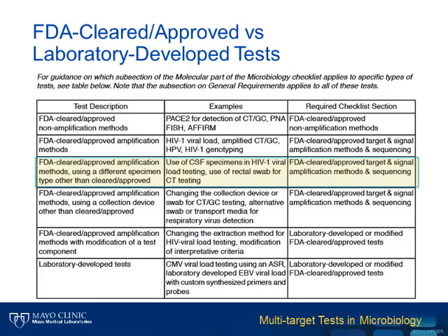The College of American Pathologists, or CAP, checklist includes a handy table to determine which parts of the laboratory checklist apply to various testing situations. FDA-approved or cleared sources require less work than laboratory-developed tests because the manufacturer has already completed a lot of the characterization of the assay. CAP allows the use of the FDA-cleared or approved target and signal amplification methods and sequencing checklist in the situation of a non-FDA-approved or cleared specimen source. An example of this might be the use of bronchoalveolar lavage specimens on a multi-target respiratory pathogen panel that was only FDA-approved or cleared for nasopharyngeal swabs.